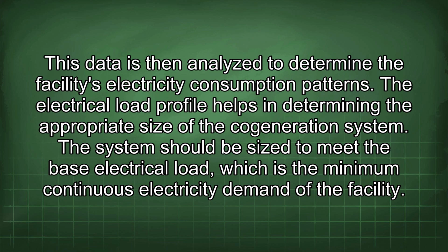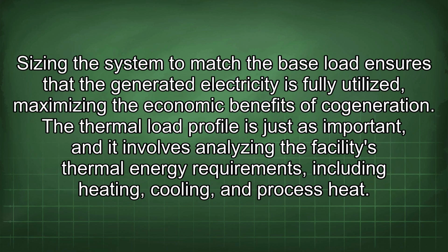The electrical load profile helps in determining the appropriate size of the cogeneration system. The system should be sized to meet the base electrical load, which is the minimum continuous electricity demand of the facility. Sizing the system to match the base load ensures that the generated electricity is fully utilized, maximizing the economic benefits of cogeneration.